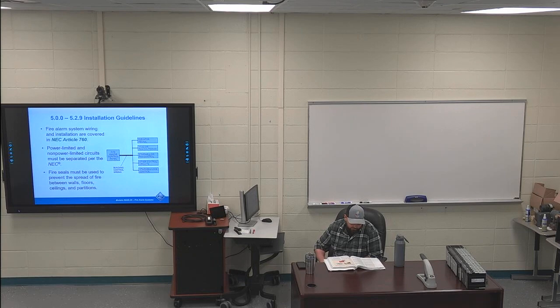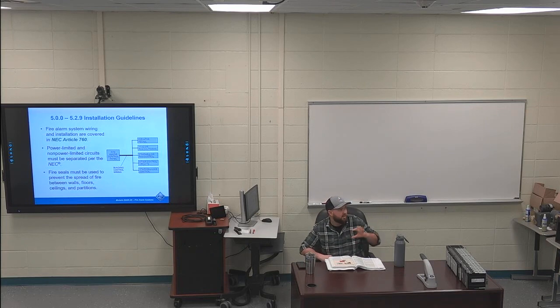Outdoor wiring, 525, first sentence is highlighted. Fire alarm circuits extending beyond one building are governed by the NEC. NEC sets the minimum requirements for wiring, just as they have all the way from electrical 1 till now. 526, fire seals. You'll see that picture for fire stopping materials. This is a big deal. Anytime you're running wire from one room to another, especially through the ceilings, it has to have fire stop in it, because you're providing a passageway. If there's a fire in this room and you're going over to welding above this ceiling, all of it has some type of fire stop in it.